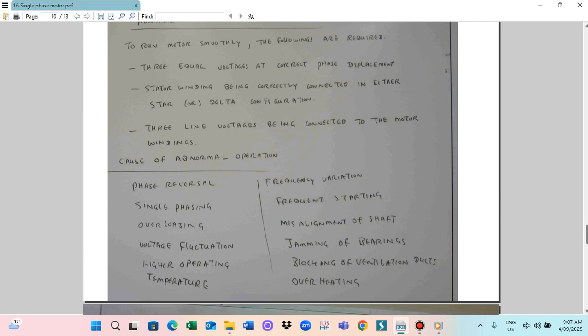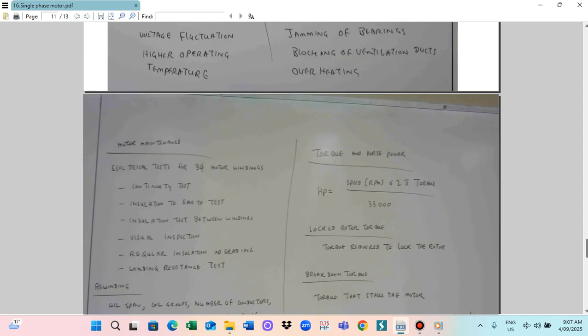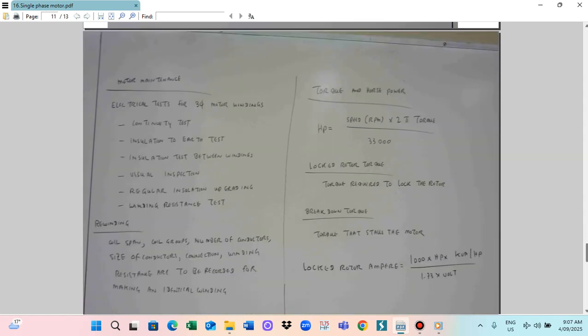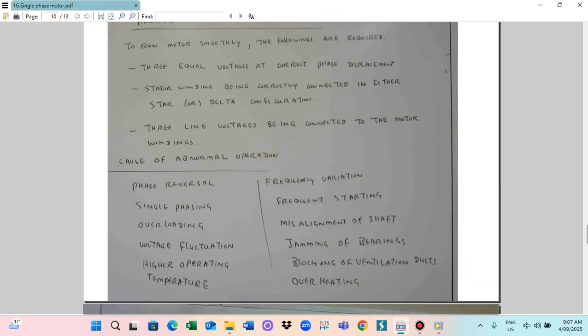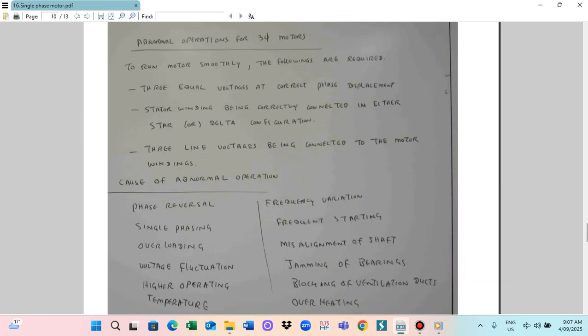And the causes of abnormal operation. So, abnormal operation of the three-phase motor. To run the motor smoothly, the following are required: three equal voltages at the correct phase displacement, the winding being connected in either star or delta configuration, and three line voltages being connected to the motor's winding. So the abnormal conditions that can happen are phase reversal or single phasing, overloading, voltage fluctuation, high operating temperature, frequency variation, frequent starting, misalignment of the shaft, jamming of the bearings, blocking of ventilation ducts, and overheating. Those are the causes of abnormal operation of motors.